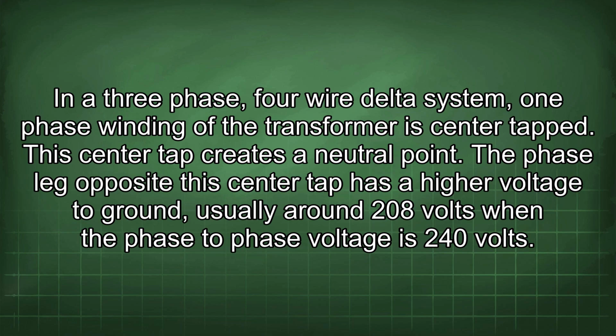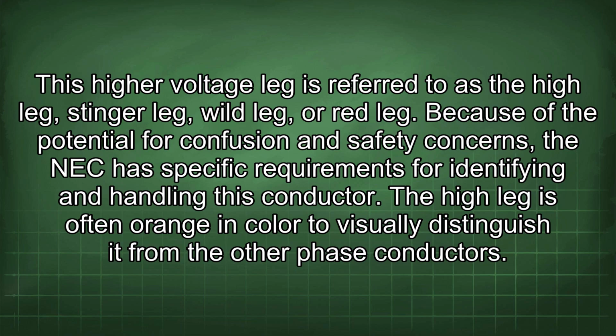The phase leg opposite the center tap has a higher voltage to ground, usually around 208 volts, when the phase-to-phase voltage is 240 volts. This higher voltage leg is referred to as the high leg, stinger leg, wild leg, or red leg. Because of the potential for confusion and safety concerns, the NEC has specific requirements for identifying and handling this conductor. The high leg is often orange in color to visually distinguish it from the other phase conductors.